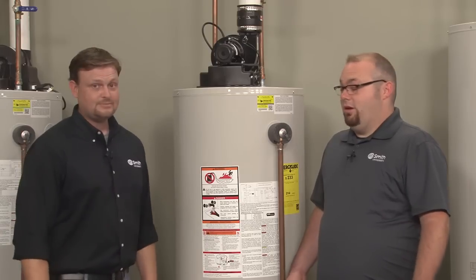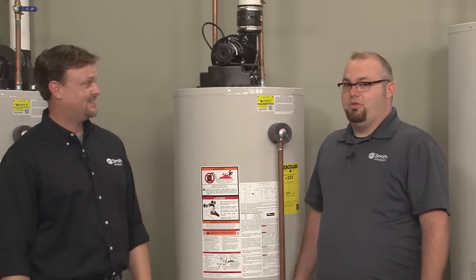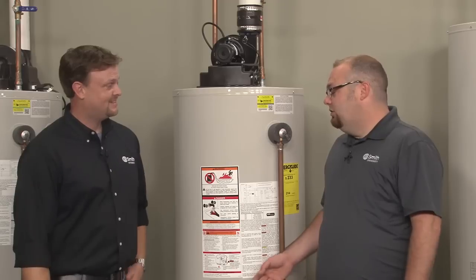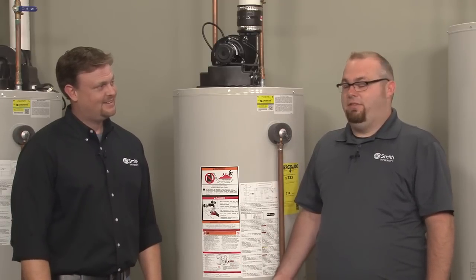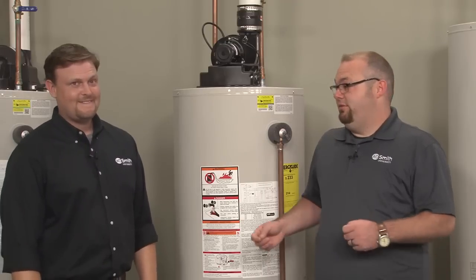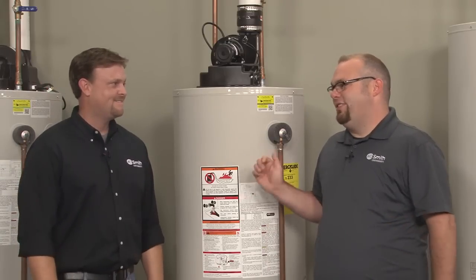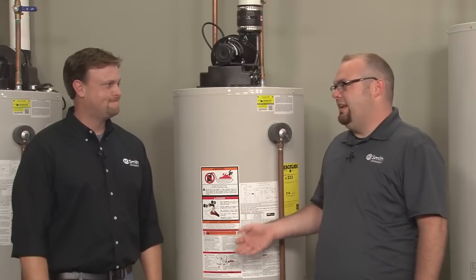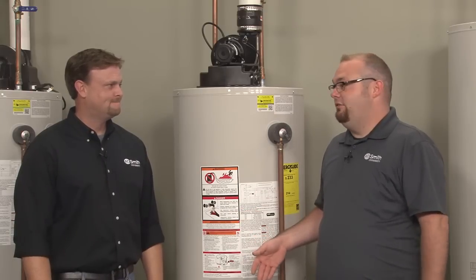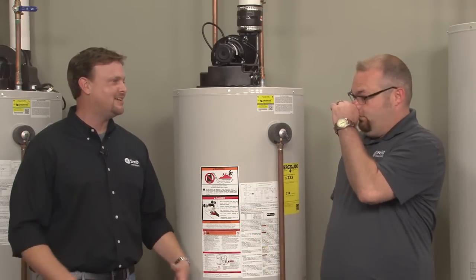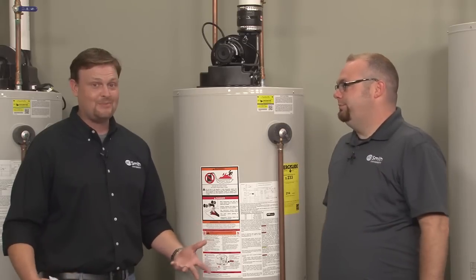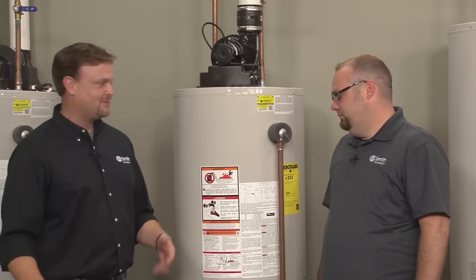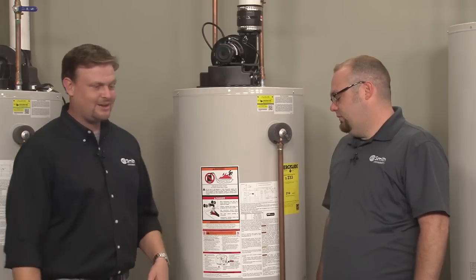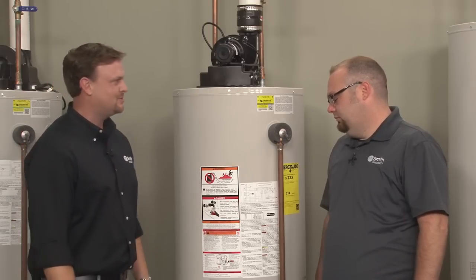Yeah, on a new install, you're going to have a large pocket of air in the gas line. So the heater, before it goes to that code, is going to try to light 3 times. And if it doesn't light, you may not have gotten all the air out of the line, so you may have to cycle power off, turn it back on to reset it. But yeah, new install, you're going to have a lot of air. That's probably why it's 3 times, they account for that. They know that's going to happen. So they typically have it try 3 times so we can get it lit.